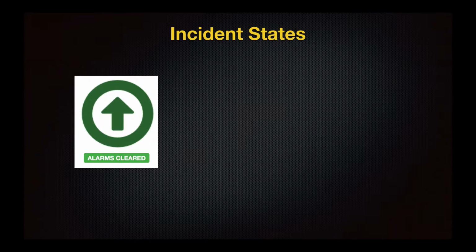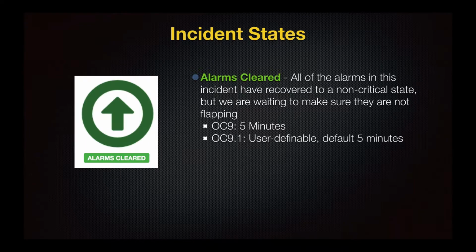There's a state called alarms cleared, and alarms cleared is basically a holding pattern that means that all of the alarms have recovered, but we're waiting to make sure they're stable before doing anything else about it. So the alarms cleared state is temporary. It typically is set to 5 minutes, and basically it's just making sure that it's not a problem that's going to recur.